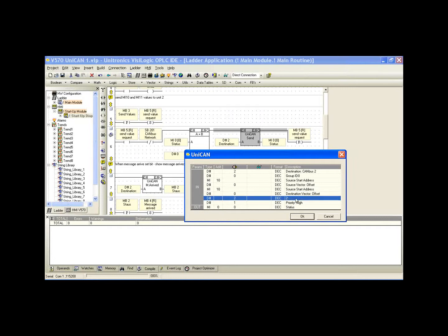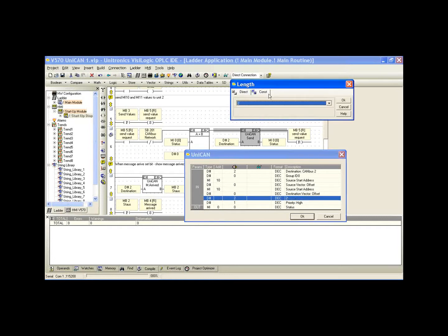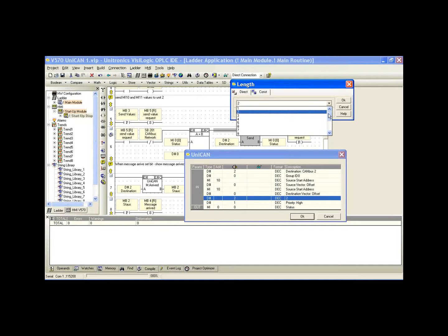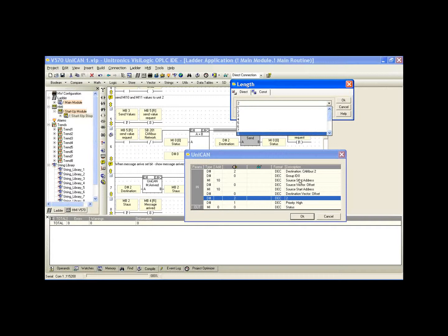Now below this, we have the length. I mentioned we can send 16 memory integers with a single send message. This is where we select this piece of information. We're sending memory integer 10 and 11. So we've selected a length of 2. If we wanted to send 16 memory integers, we can select 16. But it's important to note that this is a vector operand. What we select as the source start address is the start of the vector. We can send between 1 and 16 integers in the vector starting at the start address.